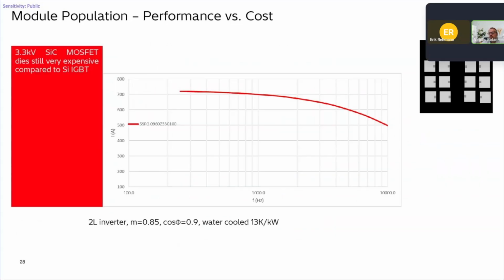Now, when it comes to performance, because we spent all this effort for silicon carbide because it promises very high performance. We see here the current output versus frequency for silicon carbide 3.3, which has what we call full population of the module. It means that on the ceramic substrate, we put as many chips as we can possibly fit, so we fill out the whole area. The characteristic of silicon carbide is that, due to the low switching losses, the dropping of the output current at higher frequencies is much milder than compared to silicon.